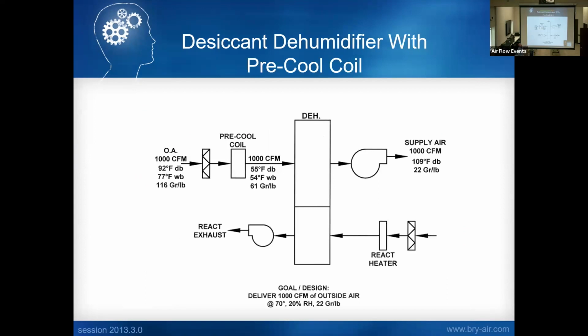Now, what we'll typically do when we need to get lower grains is pre-cooling. Again, this is to keep the energy costs down. Mechanical cooling is the lowest cost of dehumidification. So we use a pre-cool coil, typically chilled water or DX. We use both in our systems. So we're taking that same outside air at 116 grains and dropping it down to 55 saturated before we enter our desiccant rotor. And there you're able to see I'm able to get down to 22 grains, which is what I require on the outlet.